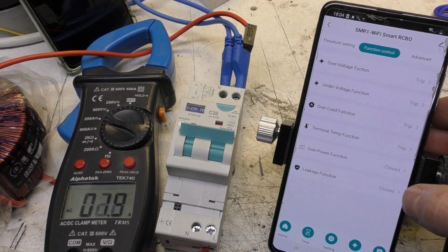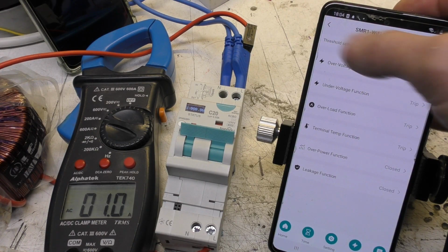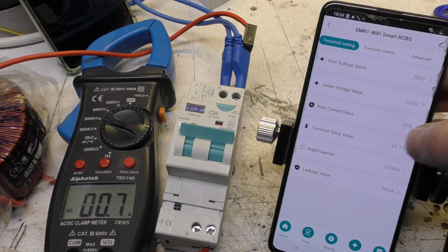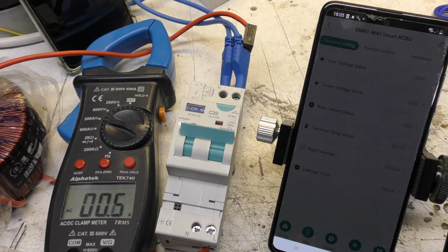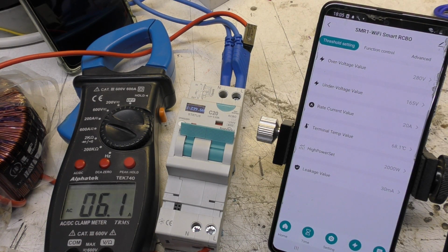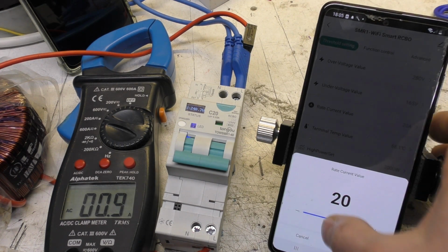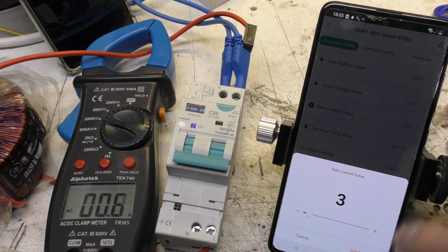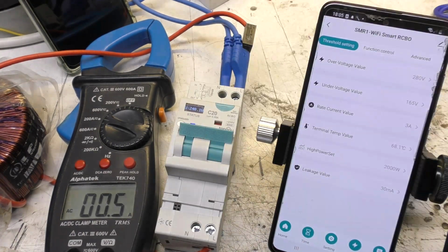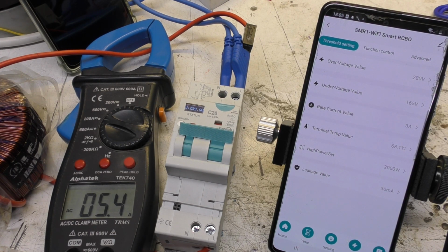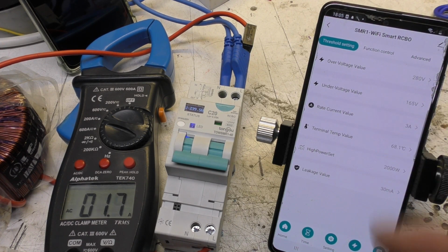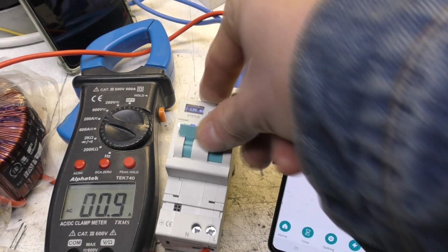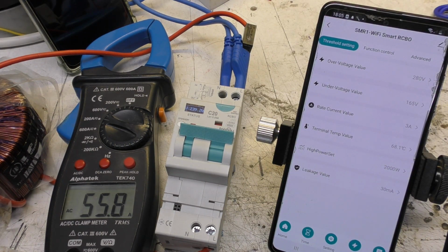So we've currently got it set to overload trip threshold at 20 amps. So if we increase the current, it's about 5 seconds delay and it does trip. We can reduce that down, so let's say we put it on 3 amps. It's now tripped. There doesn't seem to be any time characteristics, so at 3 amps, if I just crank it right up to a really high current, it doesn't seem to trip any faster.